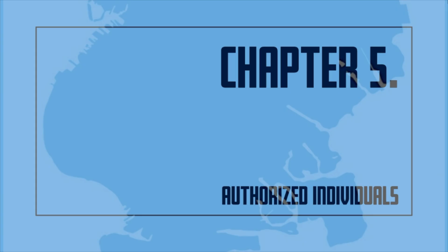3. An S-14 Certificate of Fitness holder employed by a site-specific building owner with the following certifications: the Refrigeration Operating Engineer Q99 and Q01 licenses, a High Pressure Operating Engineer's license, or a New York State High Pressure Operating Engineer's license, are permitted to perform visual inspections, test notification appliances, perform daily and weekly routine maintenance, and record all inspections, testing, and maintenance results for examination by the fire department.